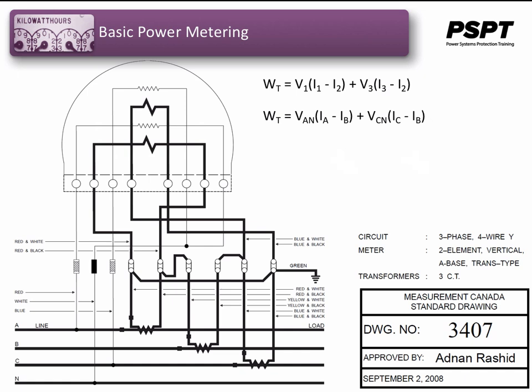If the current and voltage phasors are plotted, the resultant currents through each element are 60 degrees apart. The resultant voltages are 120 degrees apart. This 60 degree, 120 degree configuration is a standard for correct metering arrangement, and you'll see this in several of our metering arrangements. This setup, using this standard 3407, is what we would call non-Blondel compliant, and we'll explain that once we get into the Blondel section of this chapter, which is later on.